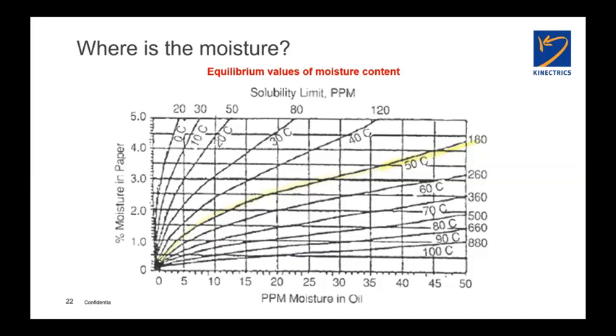But this unit operated at a temperature of about 42 degrees centigrade. And if you take that 8 parts per million now with that temperature knowledge, you're over 2% here. Well, you're 2.5%, almost 2.3% moisture content. So it has a big impact. And this was a 230 kV unit, and you do not want to have anything near 2% moisture content in paper in a unit of that voltage class. So right away we had the early hint of what caused the problem.